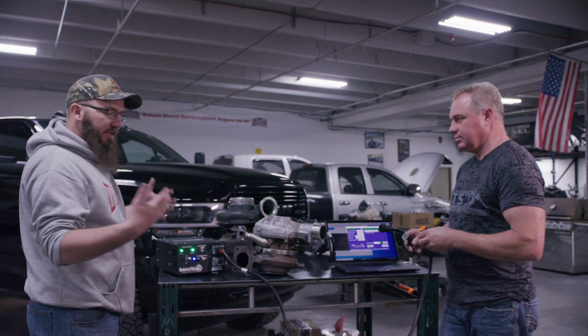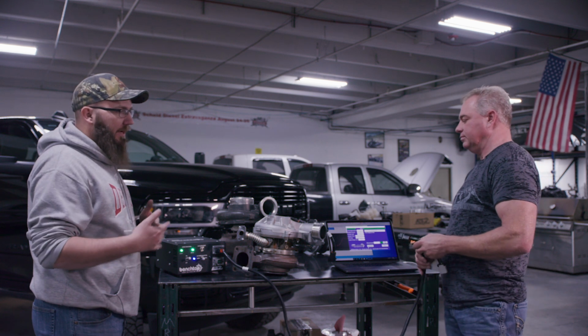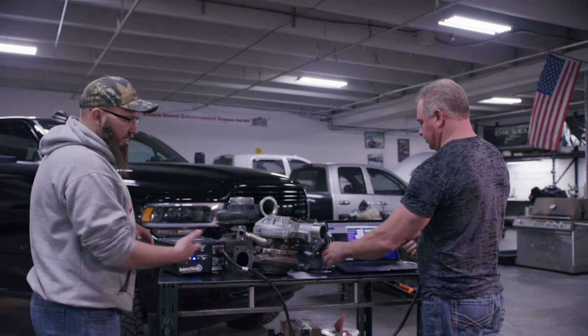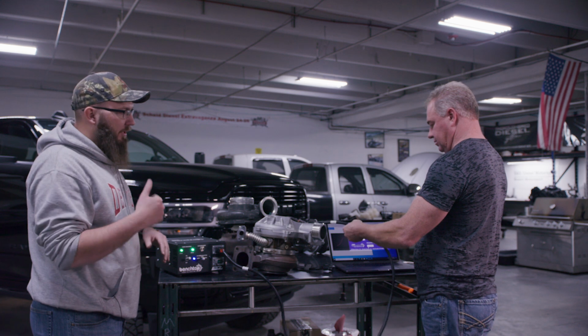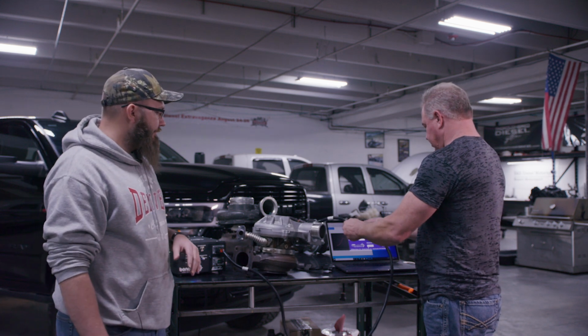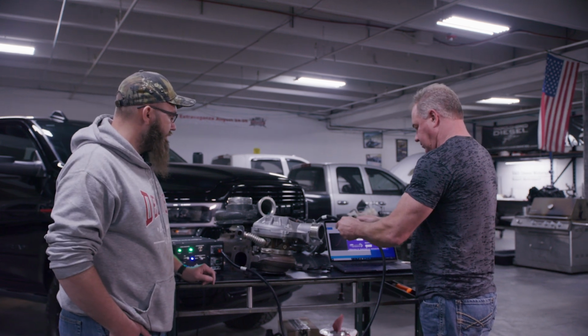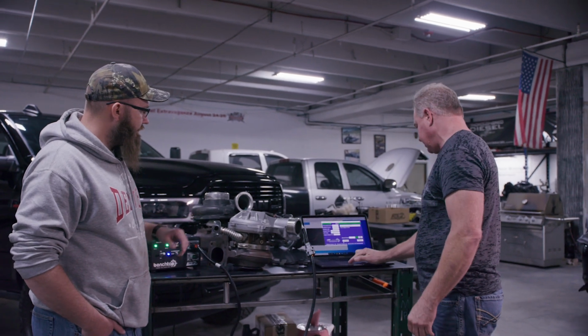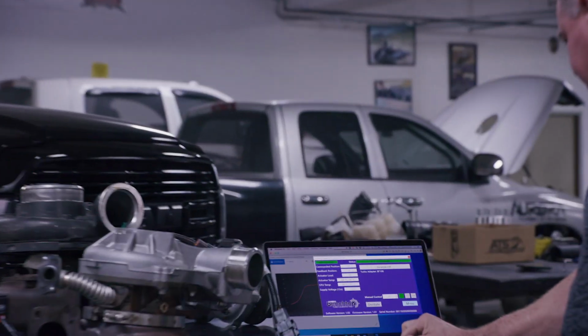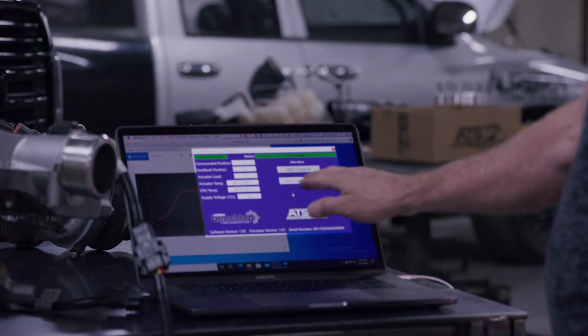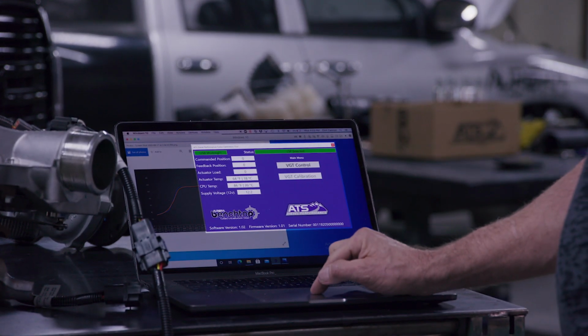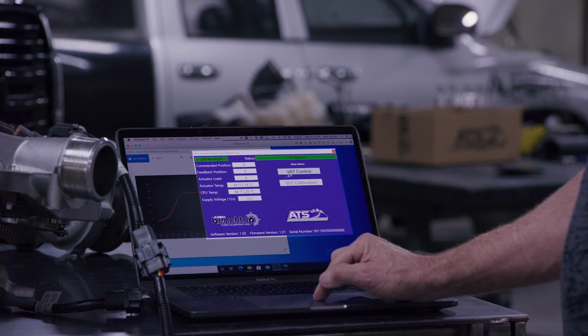And if you click it beforehand, sometimes you're fine, but most of the time what happens, it just stops communicating. You just got to turn the benchtop tester off, get everything to reset, power it back up. So we got our BT108, plug that in, and as you see, you go to menu. Guess what? The VGT calibration is not enabled because it's not an option on this turbo.